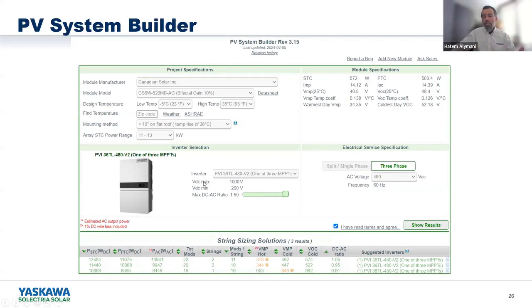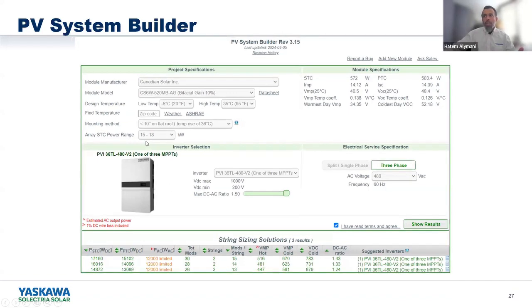So this is one example. Let's see what happens if we change the STC power range and increase it a little bit, to 15 to 18 kilowatt per MPPT. Now we see that there are other options here, so that we have 2 strings of 15, 2 strings of 14, and 2 strings of 13. We don't see any warnings here because we added more modules. So the VMP per string is actually within the VMP level of the inverter. So we are good there. We're not going to have unnecessary derating.